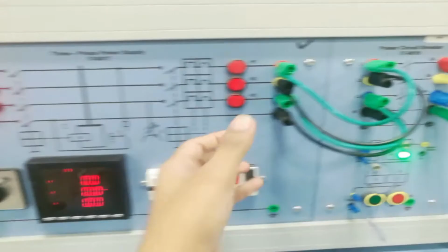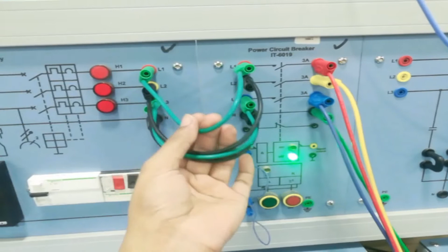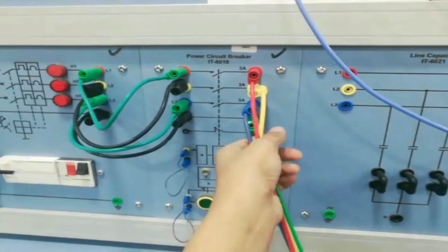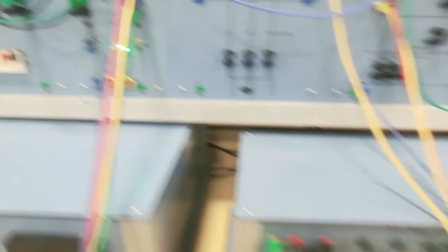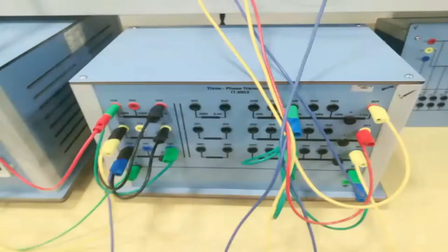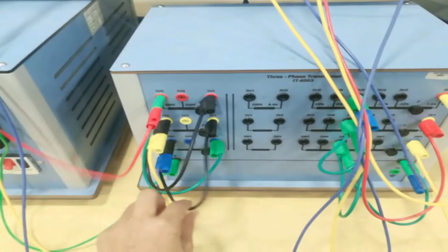You can see that the three-phase power supply is connected with the circuit breaker. We have connected each phase of the power supply with this circuit breaker, and the neutral wire is also connected with the neutral of the circuit breaker. After that, the output of the circuit breaker goes towards the transformer. This is our three-phase transformer, with its primary side and secondary side. As in the procedure, the primary side is connected in delta, so we have made the delta connection here, and the secondary side is connected in star, so we have made the star connection here.